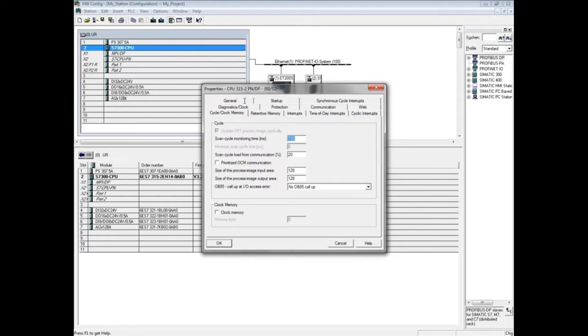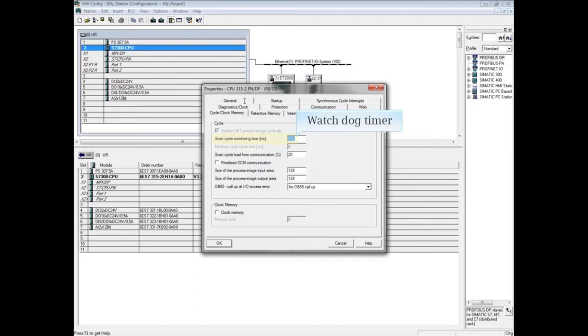The first field that can be edited is the scan cycle monitoring time, or watchdog timer. By default, the max scan cycle time is set at 150 milliseconds. This means from the time that OB1 begins until the scan is completed and OB1 begins again, you have 150 milliseconds.